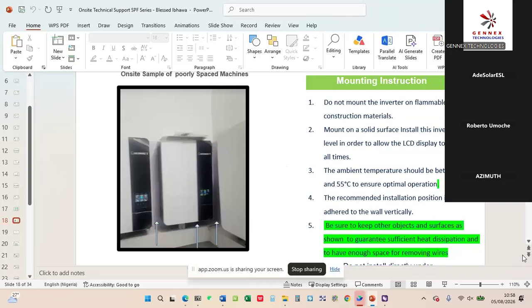They were installed in parallel, and as the arrow points there, some of us, even after installation, find it difficult to place the data logger because of the trunk, and sometimes you even block the air vent. This machine uses mechanical circulation because it has fans inside. So if you cover it with your trunk, how will the machine get the ventilation it needs? Looking at the side of the machine, you can see air vents where the fan takes in air and expels it from the left and right side. If that place is blocked, where will the air that needs to be expelled go? It will go back into your IGBTs and MOSFETs, damaging them, and then you get different types of errors. This can basically be avoided.